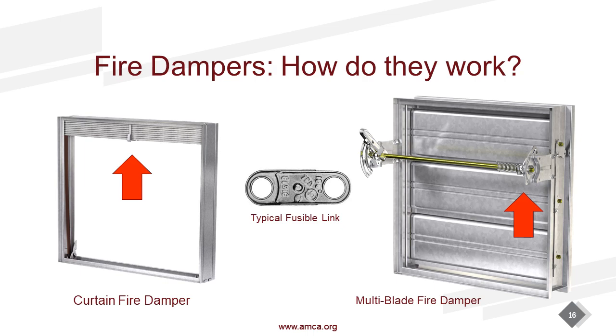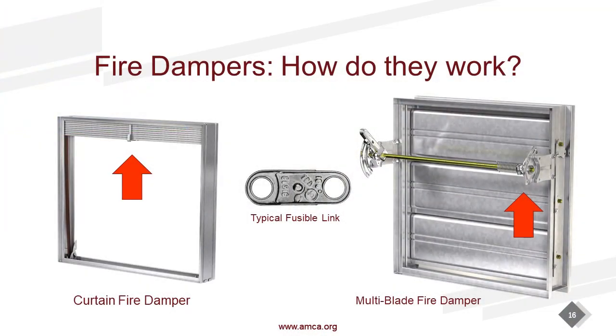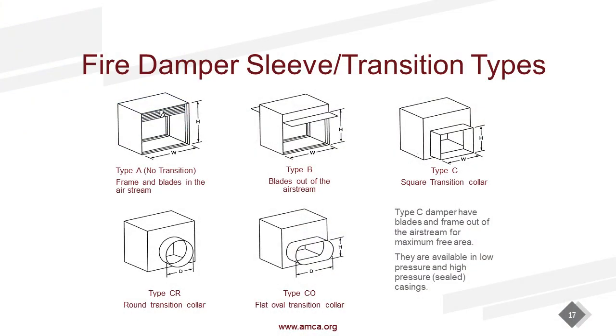Think of at home when you pull your curtains, you pull that little drawstring, the blades drop. Very similar action. This has a helical spring attached to the jack shaft on the right-hand side. When that fusible link melts, that spring uncoils, spinning that jack shaft. If those blades were open, they would slam closed. Right? So it's automatic, instantaneous closure once we reach the set point of that fusible link. 165 is common. We do see 212. We do see 286. So fire dampers and combination fire smoke dampers, most installations require a sleeve.